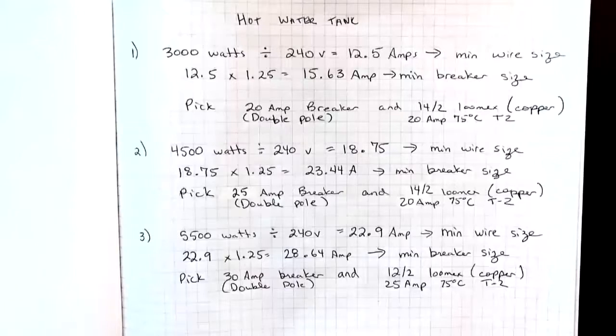Then because our breaker has to be 125 percent larger than the ampacity of our load, we take 12.5 multiplied by 1.25. This gives us 15.63 amps and that gives us our minimum breaker size.